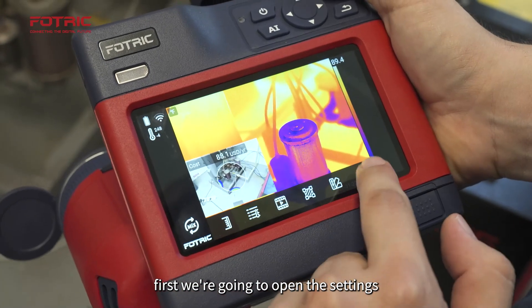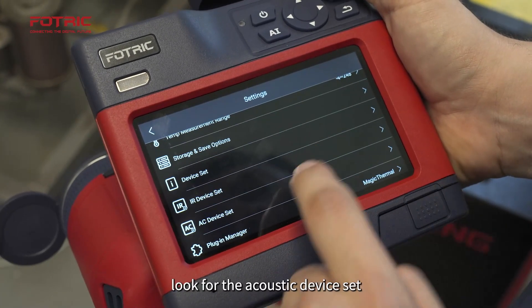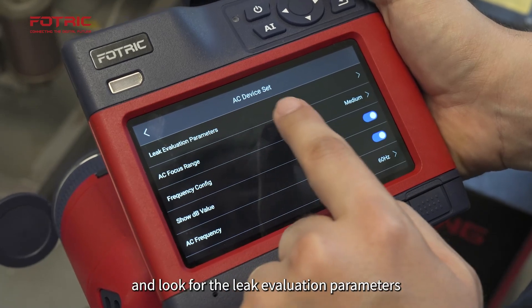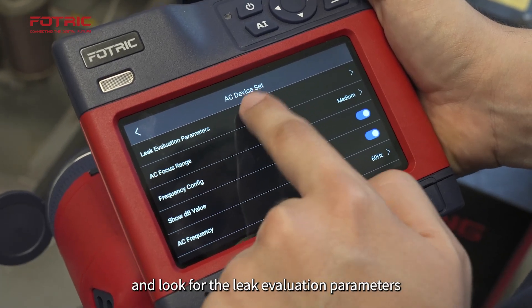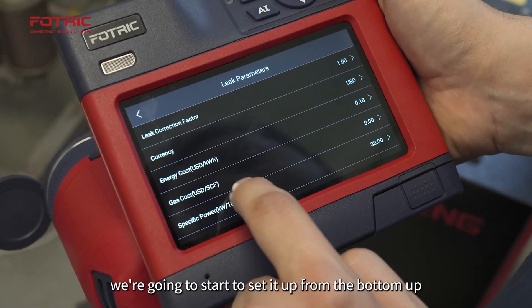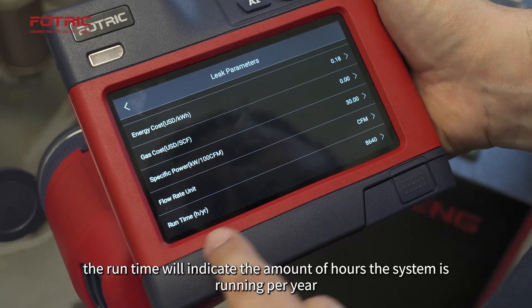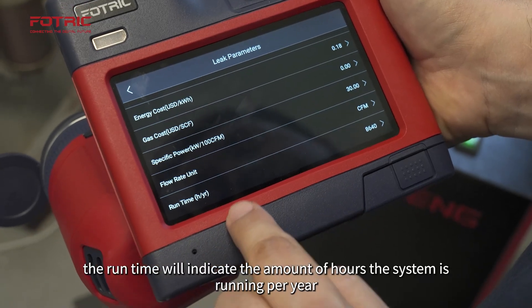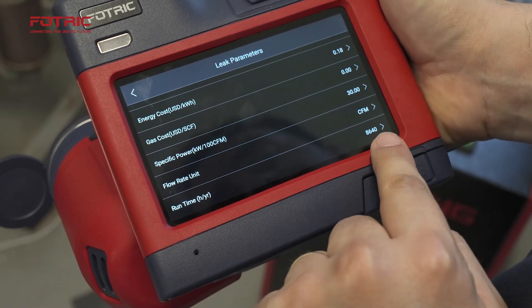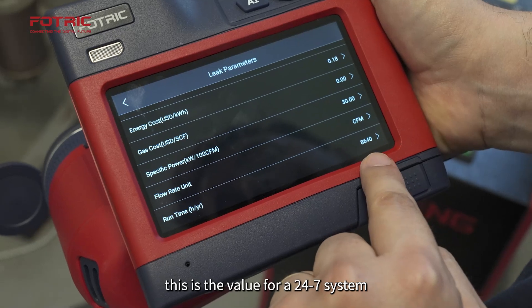First, we're going to open the settings, look for the acoustic device set, and look for leak evaluation parameters. We're going to start to set it up from the bottom up. The run time will indicate the amount of hours the system is running per year. This is the value for a 24/7 system.